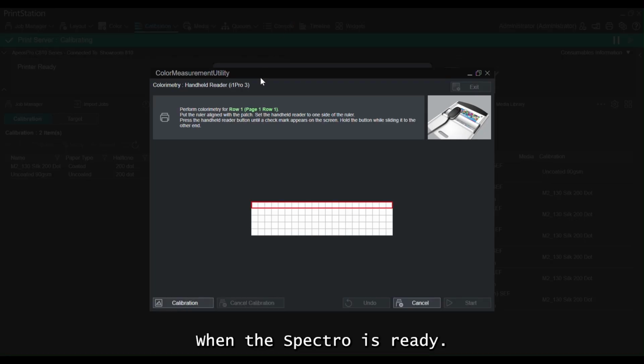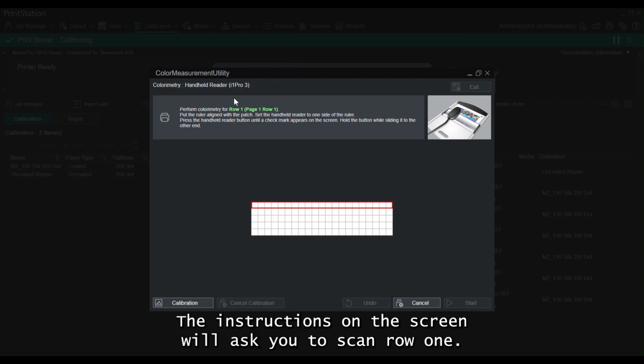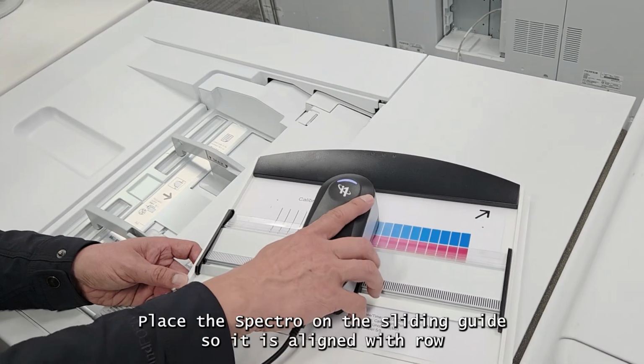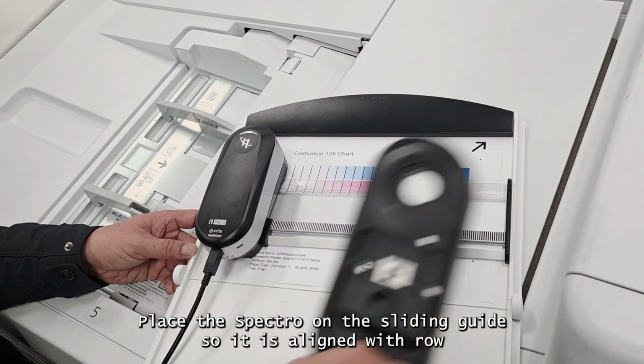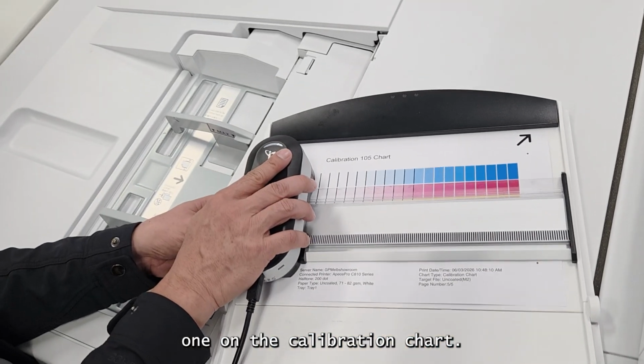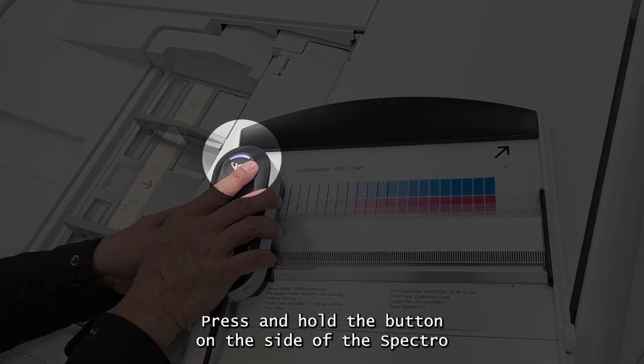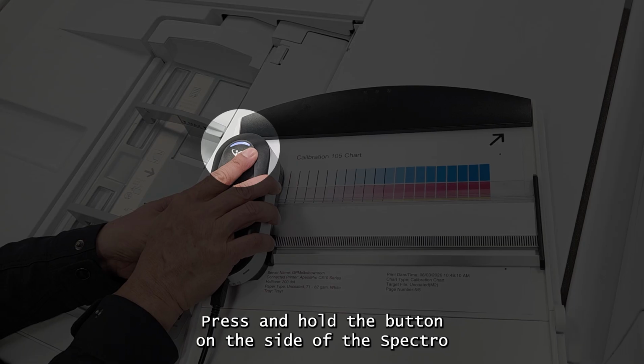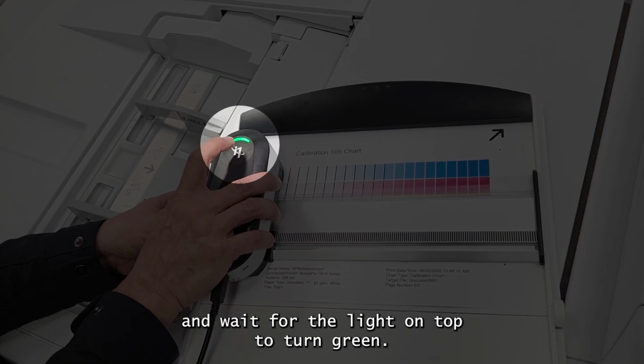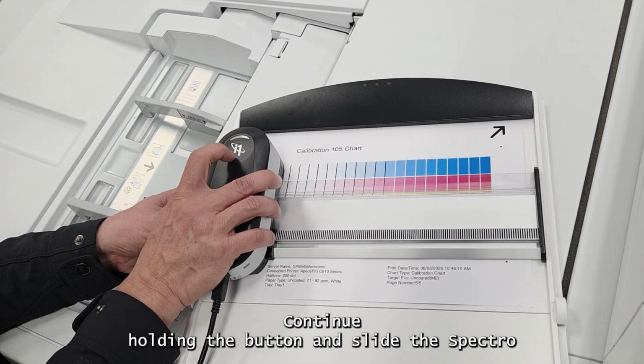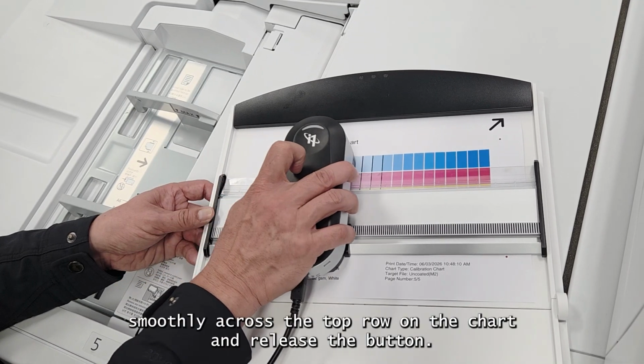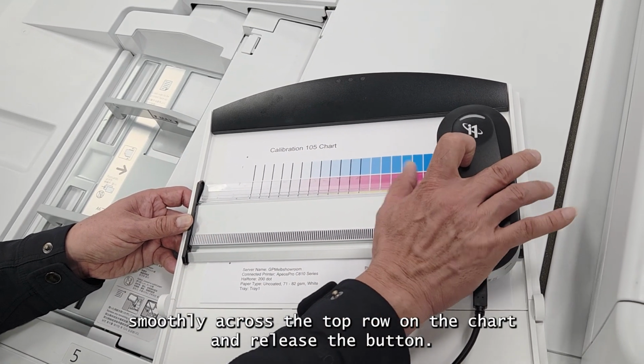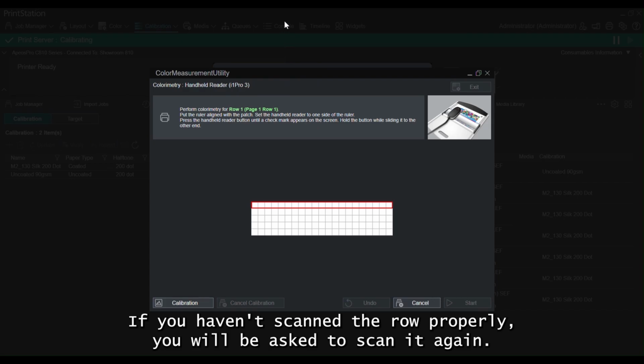When the spectro is ready, the instructions on the screen will ask you to scan row 1. Place the spectro on the sliding guide so it is aligned with row 1 on the calibration chart. Press and hold the button on the side of the spectro and wait for the light on top to turn green. Continue holding the button and slide the spectro smoothly across the top row on the chart and release the button. If you haven't scanned the row properly, you will be asked to scan it again.